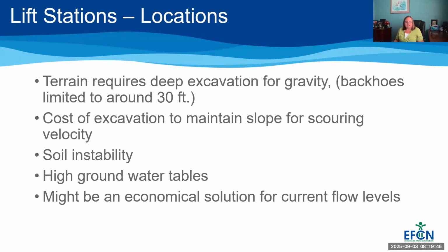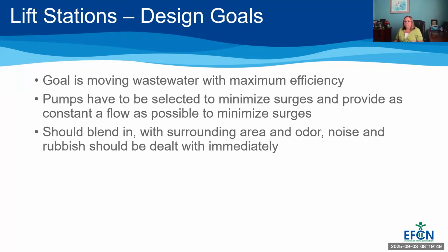And then lift stations, the design goals, the goal is obviously to move the wastewater with maximum efficiency. We don't want to be spending money to pump water in a way that's wasting a lot of energy, a way that's wasting a lot of pipe diameter, things like that. So when we're designing that lift station, we want to design it to have maximum efficiency. So we have to understand things like flow rate, how much flow is entering that lift station, how many homes or businesses or other users are connected to that particular section. So the goal there is to maximize efficiency.